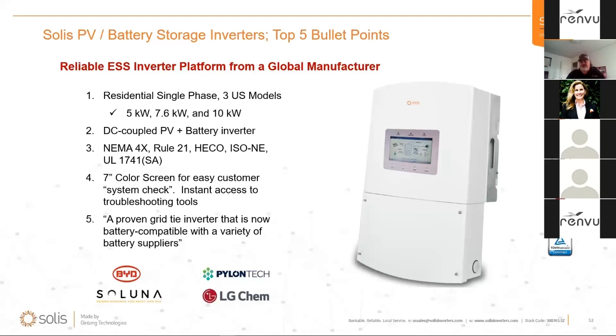Here in the US we have a generously sized wire box where you can fit your hands in to do wiring on our really positive spring terminals. I really like them, they give a great connection. There are fused battery terminals in here, and both RS-485 and CAN bus connections for battery communications. We'll be using the CAN bus type for this particular inverter and the BYD configuration.